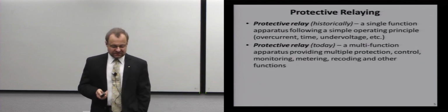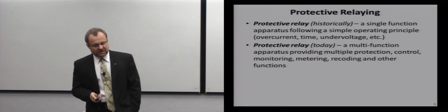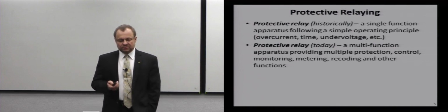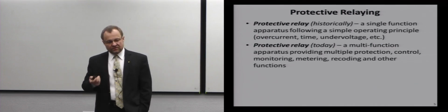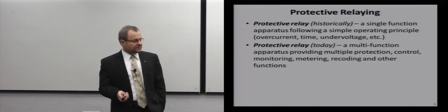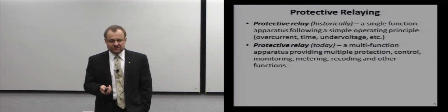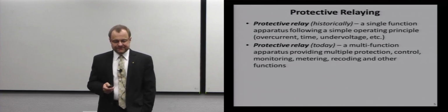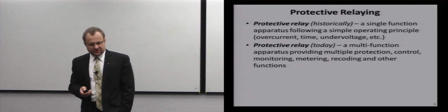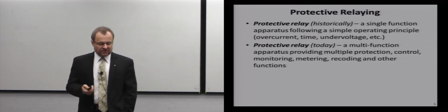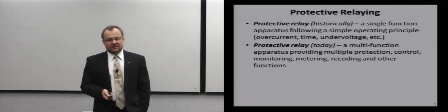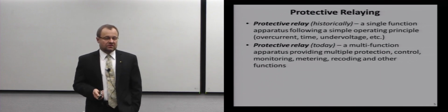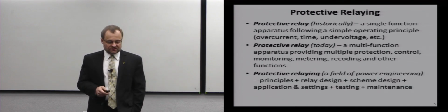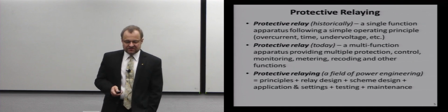Today, a protective relay is a multifunction apparatus that provides multiple protection functions. So you could have overcurrent, undervoltage, overfrequency, underfrequency, differential, all in one device. It also provides for control, monitoring, metering, recording, and other functions. And you could guess it's built on a microprocessor. It's all digital. So what is protective relaying?